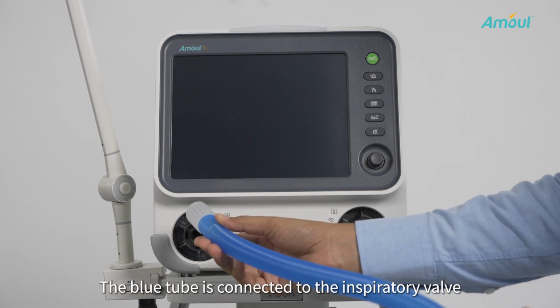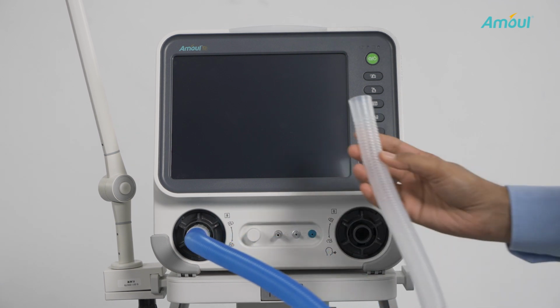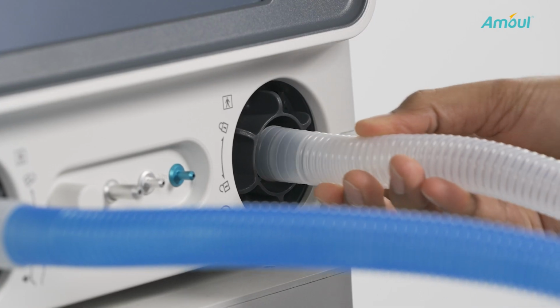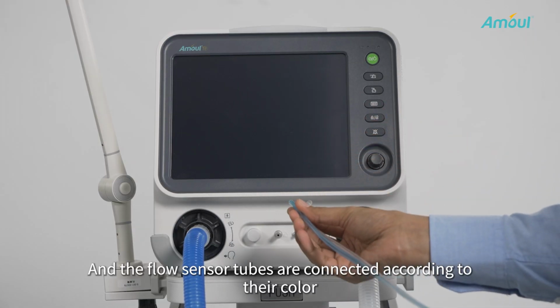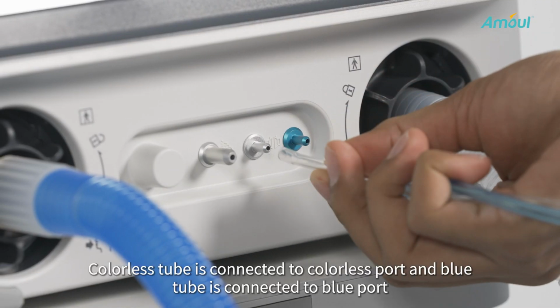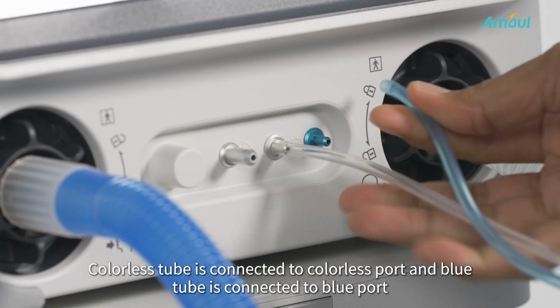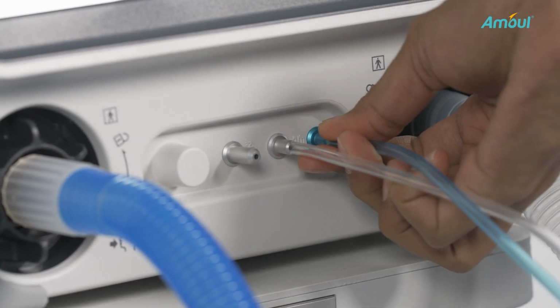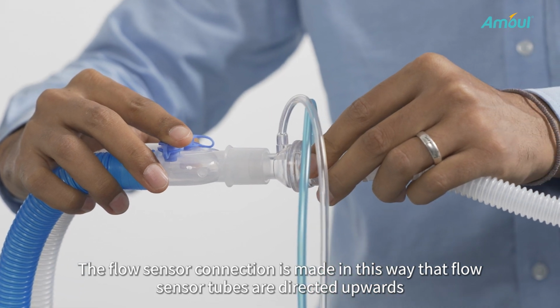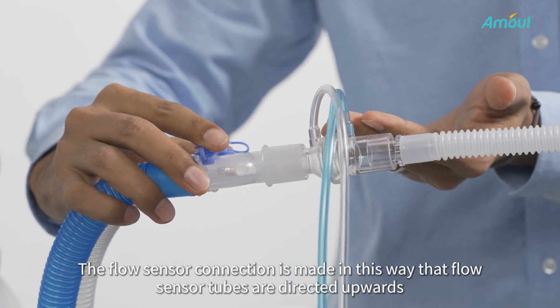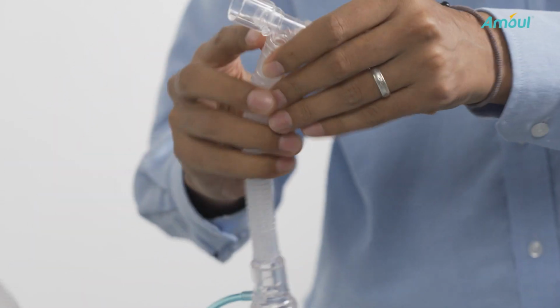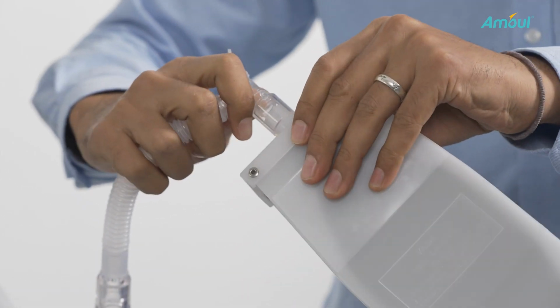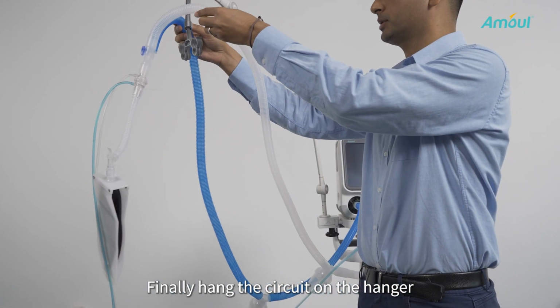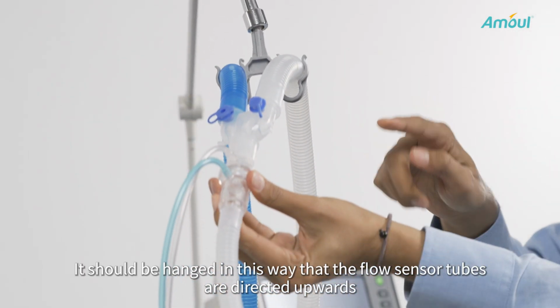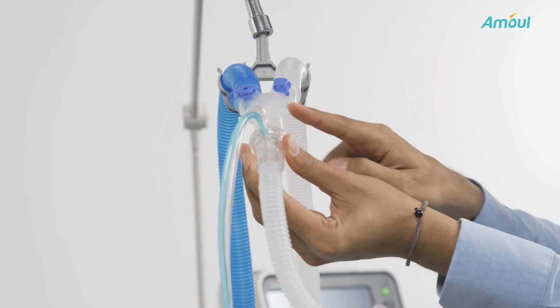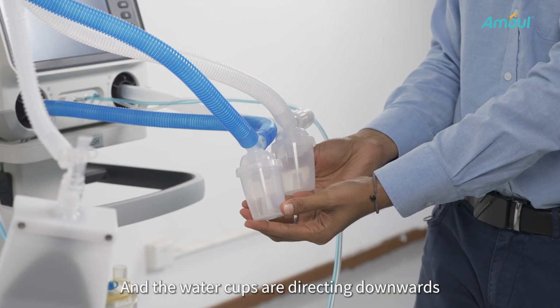The installation of the breathing circuit has a few steps. The blue tube is connected to the inspiratory valve. The white tube is connected to the expiratory valve. And the flow sensor tubes can be connected according to their color. The colorless tube is connected to the colorless port. The blue tube is connected to the blue port. The pressure sensor connection is made in such a way that the pressure sensor tubes are directing upwards. Then connect the test lung or the patient mask. Finally, hang the circuit on the hanger. It should be hung in such a way that the pressure sensor tubes are directing upward and the water cups are directing downwards.